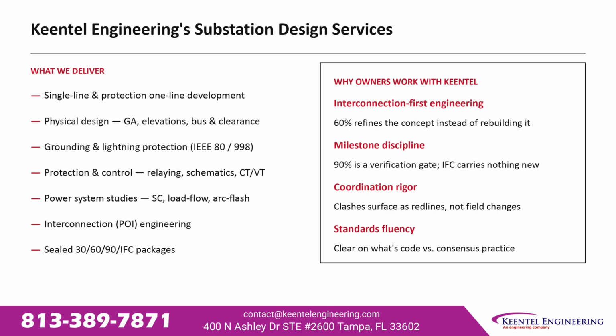The substation design services span the full milestone sequence. Electrical deliverables include single line and protection one-line development, physical design covering general arrangement, elevations, bus layout, and clearance, grounding and lightning protection per IEEE 80 and IEEE 998, protection and control including relaying, schematics, and CT and VT design, and power system studies covering short circuit, load flow, and arc flash. Process deliverables include interconnection engineering at the point of interconnection and sealed 30%, 60%, 90%, and IFC packages.